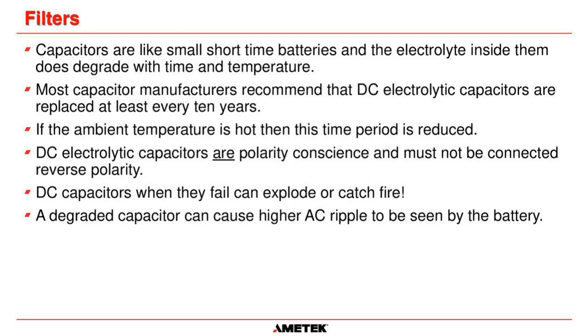Please remember, DC electrolytic capacitors are polarity conscious - they cannot be connected in reverse polarity. You will have a very bad day if you do that. It will probably let the magic smoke out of the capacitors, and believe me, it's like a David Copperfield magic show when that happens - it goes everywhere. So really make sure you check, double check, and triple check your positive and negative symbols on your capacitors if you are replacing them yourselves. DC capacitors, when they fail, can explode or catch fire. That's why we recommend they're replaced, because when they do degrade, their failure method can be exploding or catching fire, and it has happened on many occasions, okay?